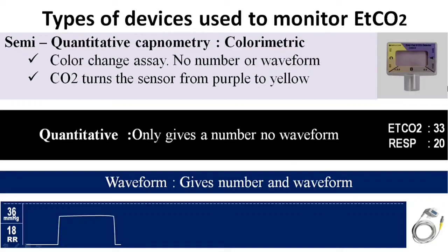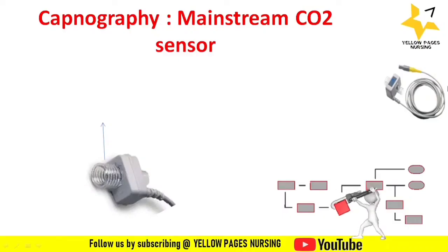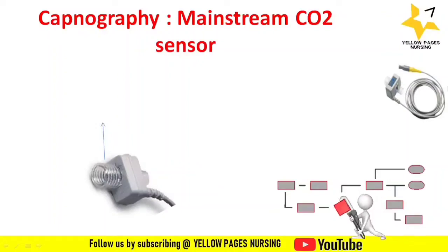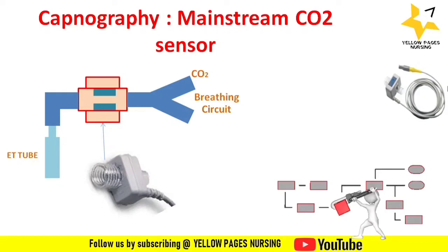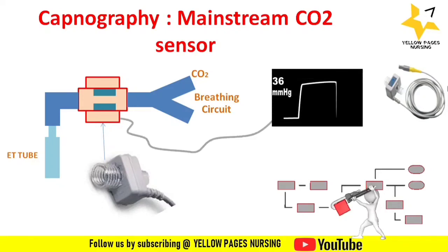Now, the capnography device setup: there are many types of CO2 sensors, including mainstream, sidestream, and microstream CO2 sensors. For the mainstream CO2 sensor setup, the sensor is connected at the terminal end of the ET tube, the breathing circuit is connected at the other end of the sensor, and the cable from the sensor connects to the monitor to display the CO2 waveforms.